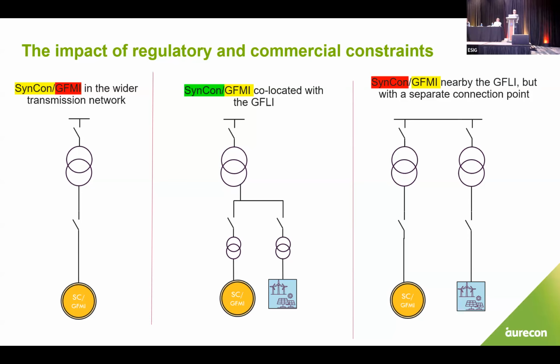Starting from the left-hand side, the first solution is to install a synchronous condenser or grid-forming battery in the wider network. The use of grid-forming inverters isn't possible because the network owner can't own assets that generate megawatts. The use of a syncon has been there previously, but unfortunately that's one of the concerns with these system strength charges.